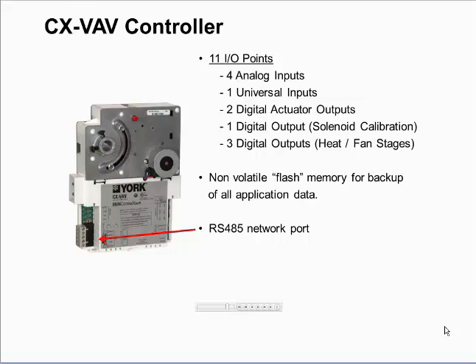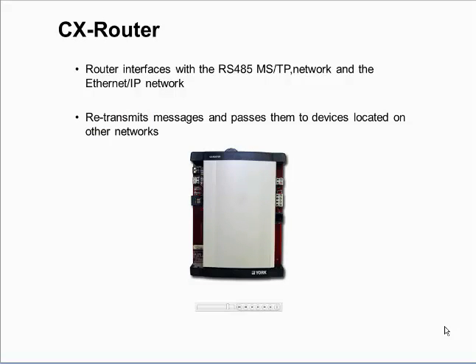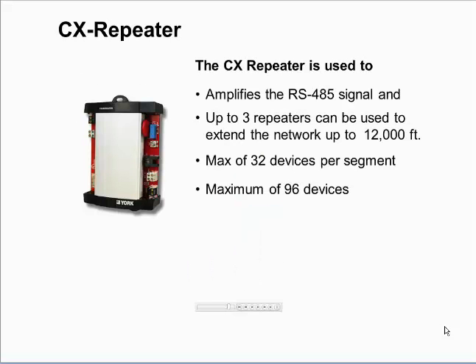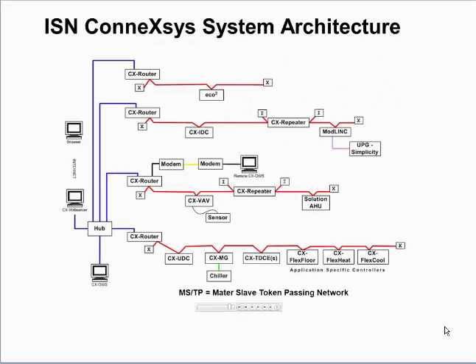The CX router interfaces with the RS-485 network and the Ethernet IP network. It resends messages to devices on other connected networks. The CX repeater is used to amplify and extend the RS-485 signal. Up to 3 repeaters can be used to extend the network up to 12,000 feet. This is a diagram of the architecture of the ISN ConneXsys control system network. In red is the ISN RS-485 network of controllers and other devices. On the left side of the chart are the CX routers which connect the RS-485 networks with the facility's Ethernet networks shown in blue.